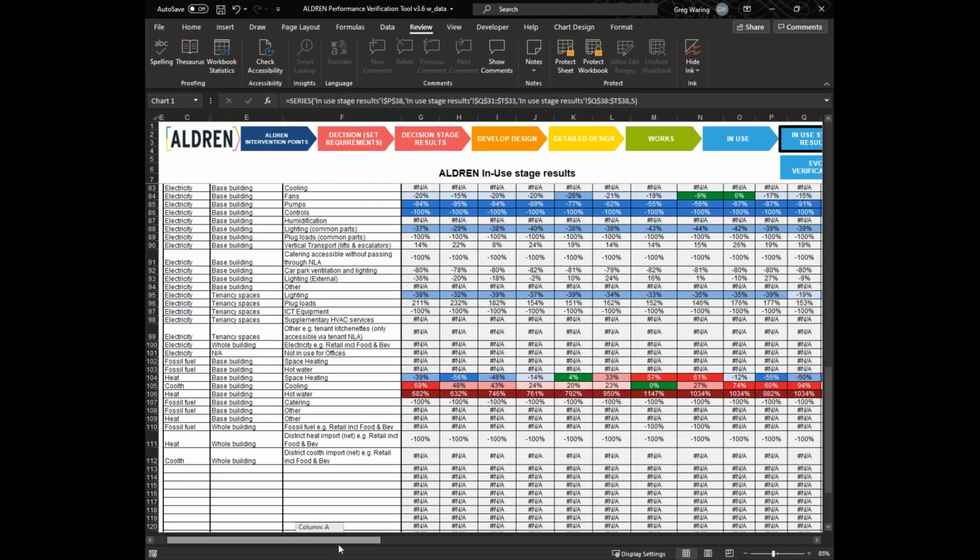When you look at the seasonal profile, you can see that the colour coding is indicating much higher heating use in the summer than expected, and lower heating use in the winter than expected. Whereas in the case for the cooling, red colour codes give higher consumption in the actual data.